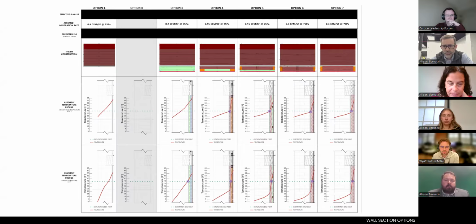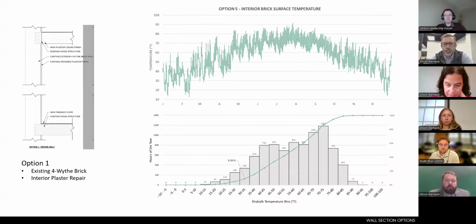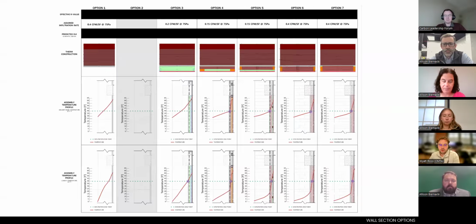Being historic preservation, we couldn't add anything to the exterior of the building because that would impact the existing cladding. We had options to potentially fur up to 5 inches into the interior of the existing exterior wall, then finish with the same plaster finish. So we were exploring options within a pretty thin margin, about 5 inches to work with, considering what types of insulation and furring we could use, and then understanding the temperature profiles of those walls and the risk that posed.